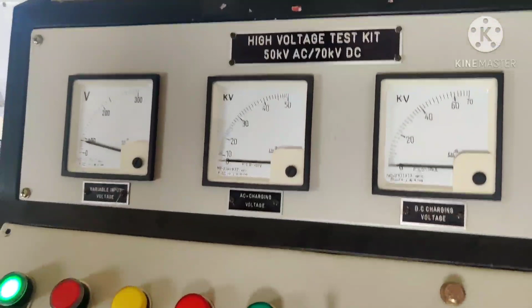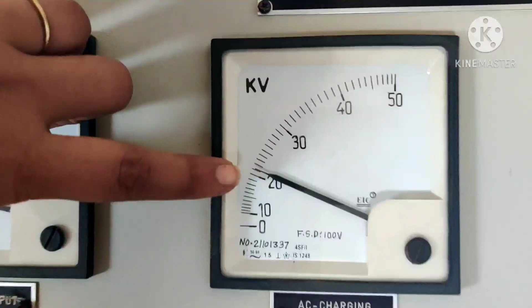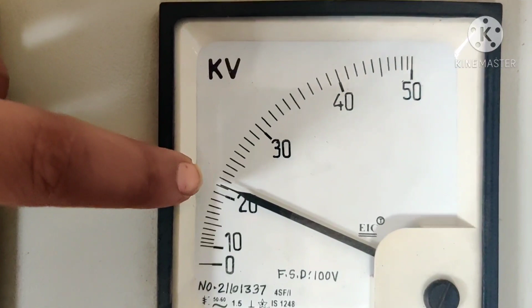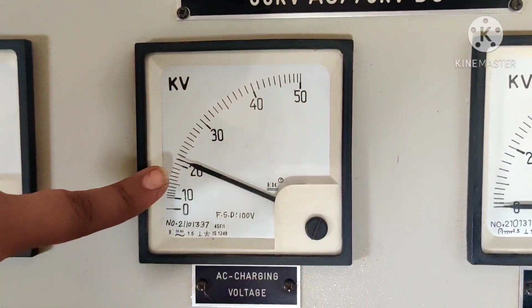So the breakdown has occurred. The pointer is reading 0 now. So what was the reading at which the breakdown took place? We push the memory push, and you can see the reading here. So it is 21 kilovolts. For 10 mm of gap length, 21 kilovolts is the breakdown voltage.